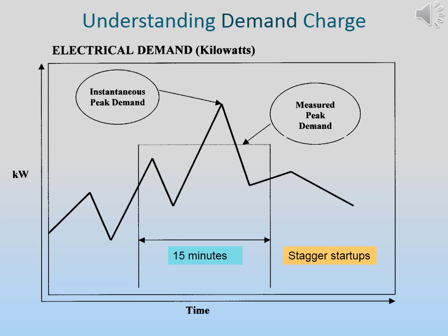Is there anything that we can do to minimize this peak? We saw in that one tariff the demand cost was $6 per kilowatt. That is expensive. That is why it is very important to examine how and when we operate our equipment.